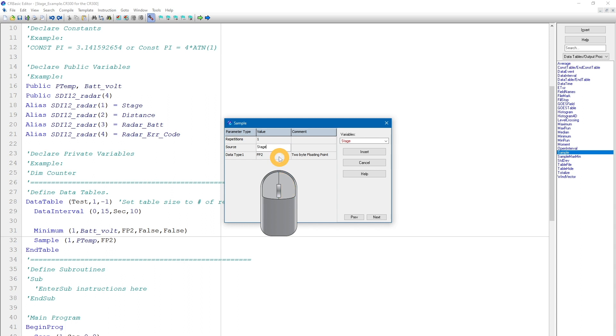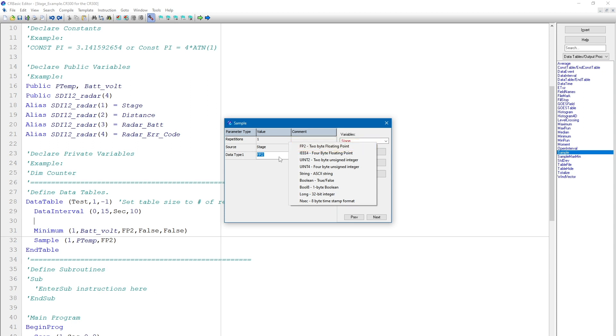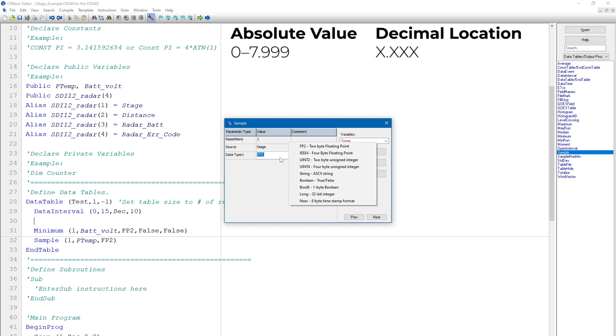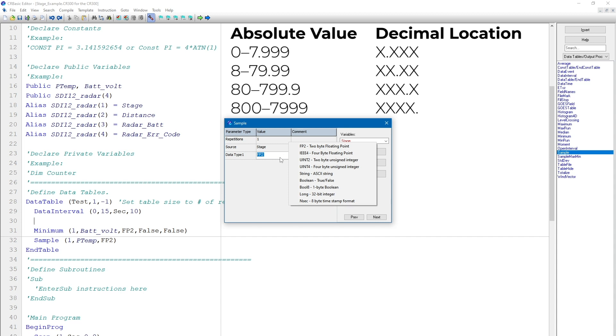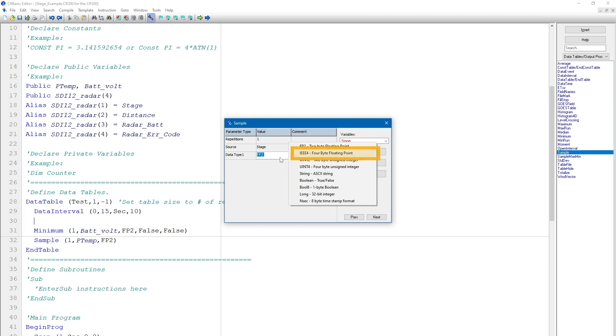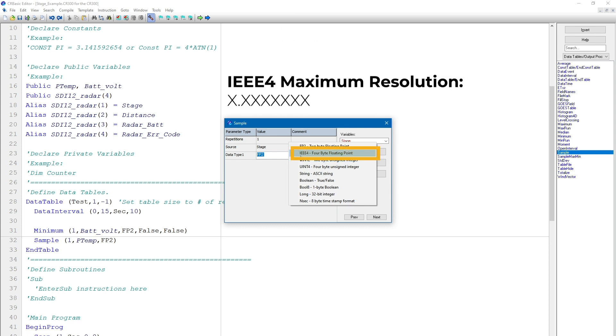I can right-click in the data type box to see a list of data types available. Each of these data types has a different range and resolution. FP2 is a floating point, 2-byte number with a maximum value of 7999, but the resolution, or places to the right of the decimal, is dependent on the magnitude of the number. For example, if the value is less than 8, then the number will have 3 decimal places. If the number is 80 or greater, then the number will only have 1 decimal place. The FP2 data format isn't a good choice.